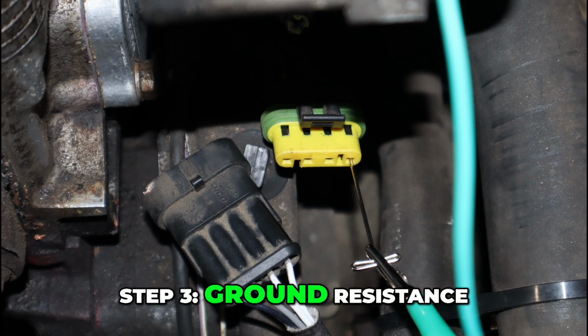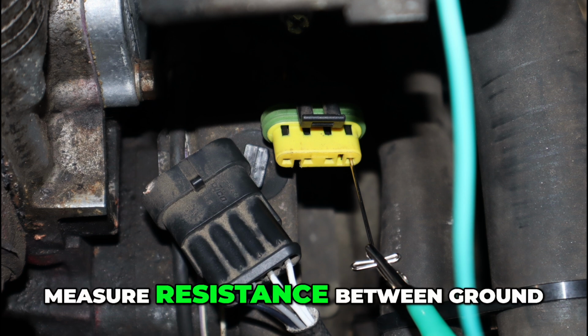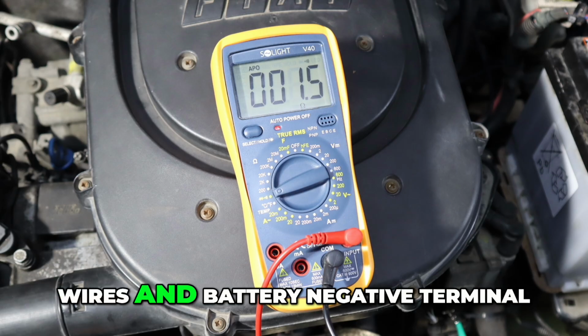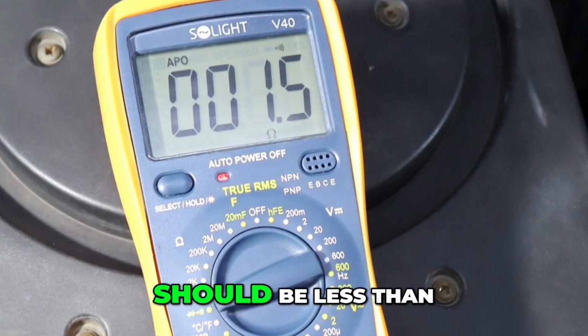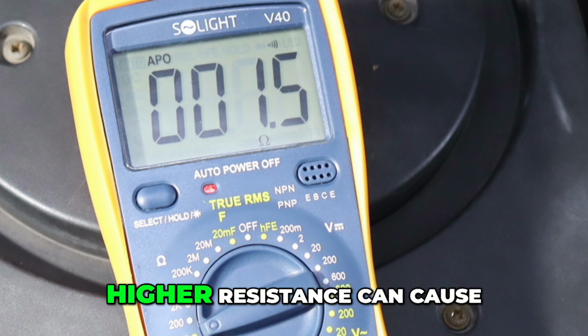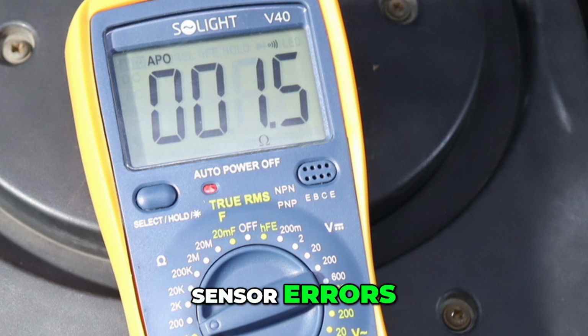Step 3, ground resistance: measure resistance between the ground wires and the battery negative terminal. It should be less than 1 ohm. Higher resistance can cause sensor errors.